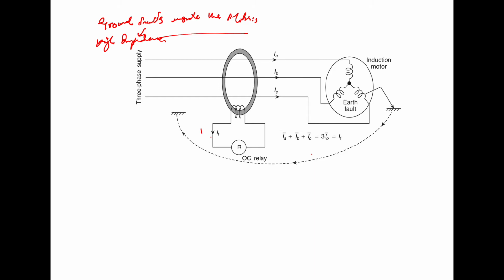Now if an electronic circuit is used to sense the voltage developed by the pickup coil, the current balance relay described can be made extremely sensitive and can detect earth fault currents down to a few tens of milliamperes. So very high sensitivity, however, is likely to cause some nuisance. So this is the ground fault inside the motor, and how we can detect that.